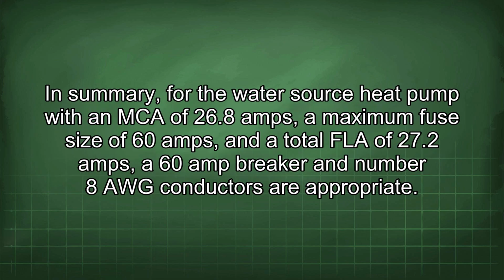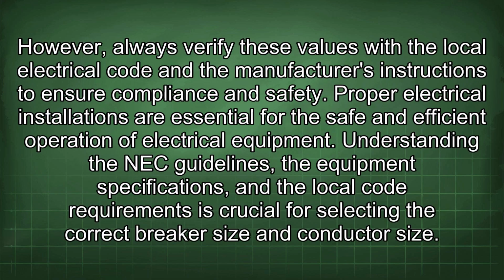In summary, for the water source heat pump with an MCA of 26.8 amps, a maximum fuse size of 60 amps, and a total FLA of 27.2 amps, a 60 amp breaker and number 8 AWG conductors are appropriate. However, always verify these values with the local electrical code and the manufacturer's instructions to ensure compliance and safety. Proper electrical installations are essential for the safe and efficient operation of electrical equipment.